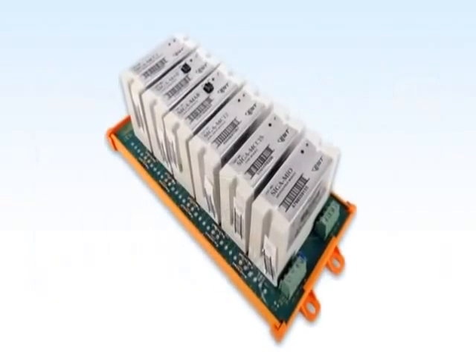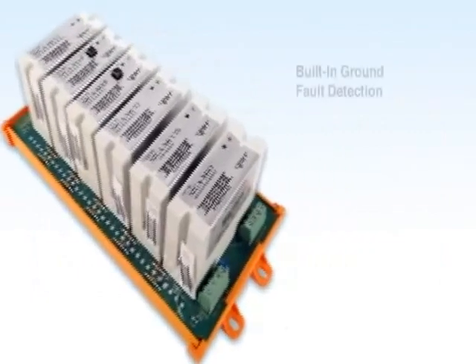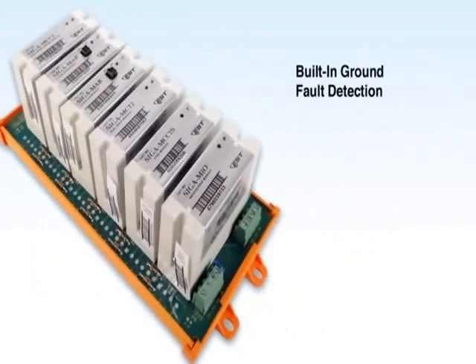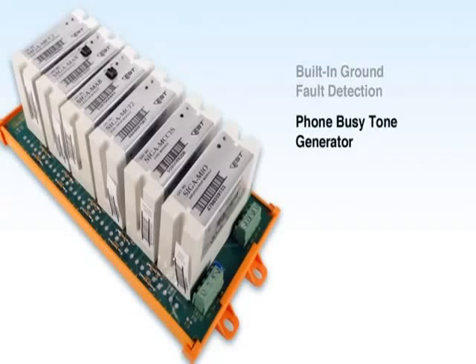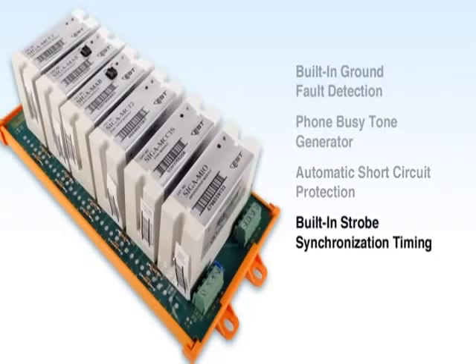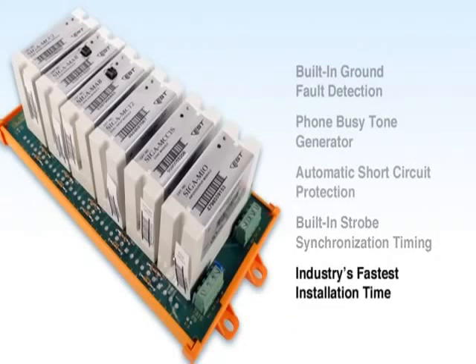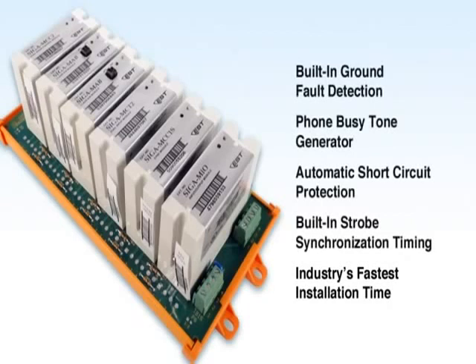Signature Series modules combine advanced technologies like built-in ground fault detection at the device, phone-busy tone generator, automatic short-circuit protection, built-in strobe synchronization timing, and the industry's fastest installation time using the multifunction SIGA UIO motherboard. Imagine installing 12 individual system inputs on the control panel in the time it takes to connect 2 wires.